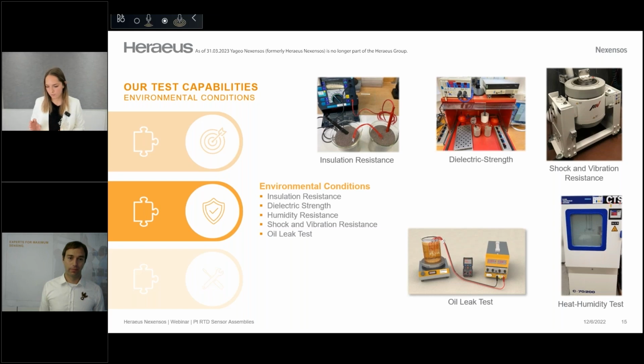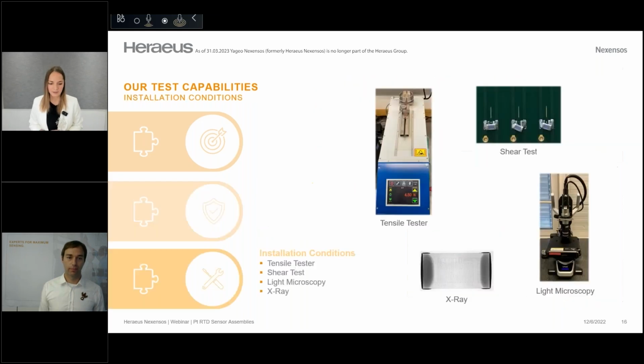And the last very crucial test setup here is the heat humidity test. So we don't only expose the sensor to a temperature, but also to humidity. And this test could also be called an 85-85 test. So we expose, for example, the sensor for 500 hours at 85 degrees Celsius and 85% relative humidity. All right, next slide.